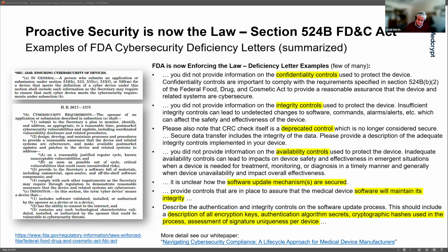It's a very important topic for protecting your devices, regardless of whether or not it's mandated by law. Yeah, good point. And to add more to that, even though the FDA has, I think, brought the regulatory cybersecurity discussion to life all the way back in 2014, other regulators have caught up and have basically leaned in the same direction as the FDA has.